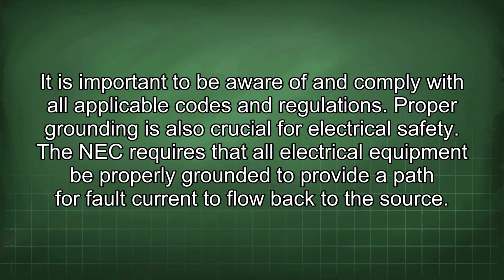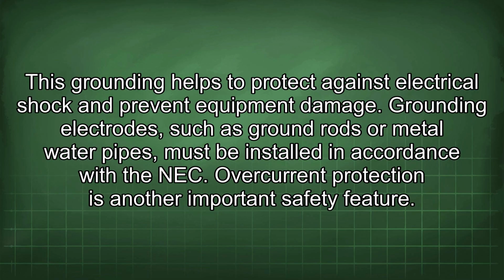Proper grounding is also crucial for electrical safety. The NEC requires that all electrical equipment be properly grounded to provide a path for fault current to flow back to the source. This grounding helps to protect against electrical shock and prevent equipment damage. Grounding electrodes such as ground rods or metal water pipes must be installed in accordance with the NEC.